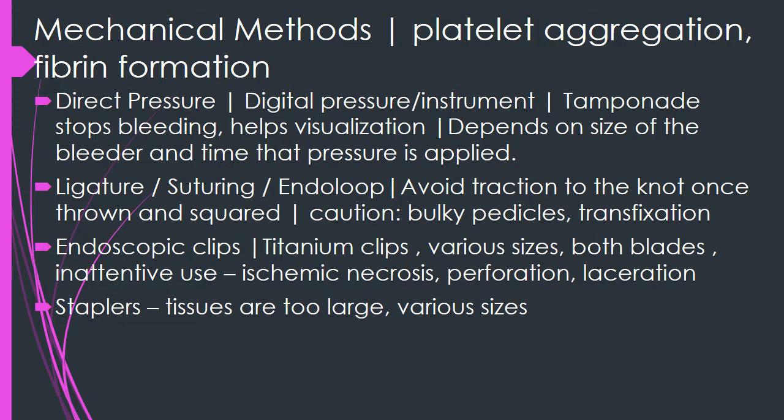Endoscopic clips are made of titanium and come in various sizes. It is required that both blades should be visible when applying the clip. Inattentive use of the clip applicator may result in ischemic necrosis of an organ, perforations, or even lacerations of tissues. It is always safer to skeletonize the blood vessel prior to application of the clips.